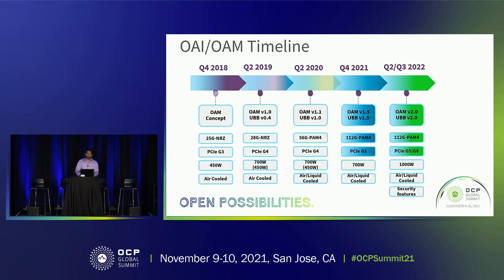Here is our evolution and roadmap. We started in 2019 with just the Open Accelerator Module, designed to support up to 450 watt TDP — pretty high for that timeframe — and high bandwidth was supported through 25 gig NRZ. Fast forward to today, we're trying to release OAM 1.5 spec in the next few weeks, along with Universal Baseboard version 1.5 spec. Within this spec, we will enable support for 112 gig PAM4, as well as PCIe Gen 5 and 700 watt TDP per accelerator. The UBB has up to eight accelerators, so we're talking about close to six kilowatts just for baseboard power delivery.